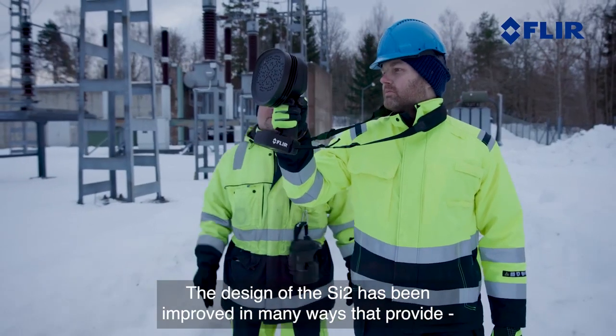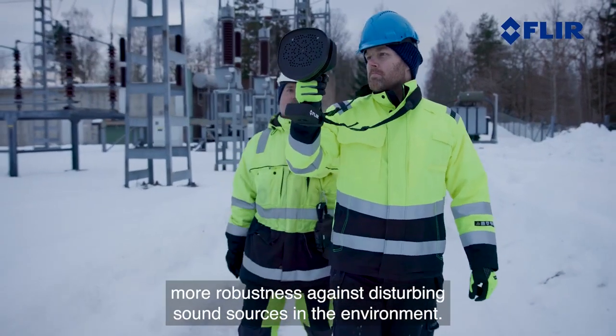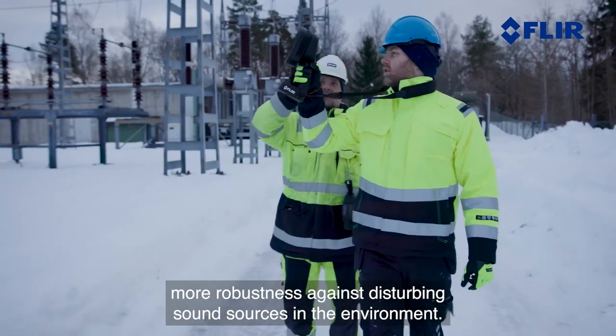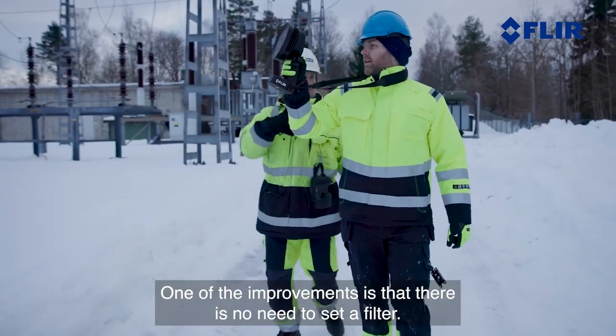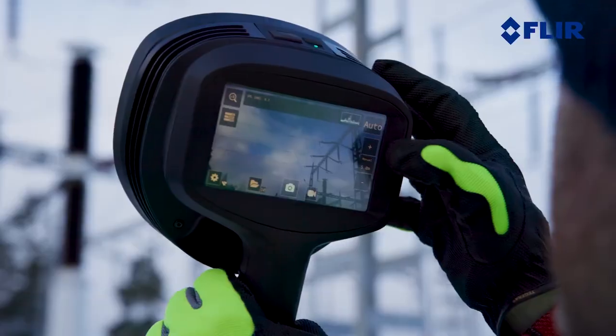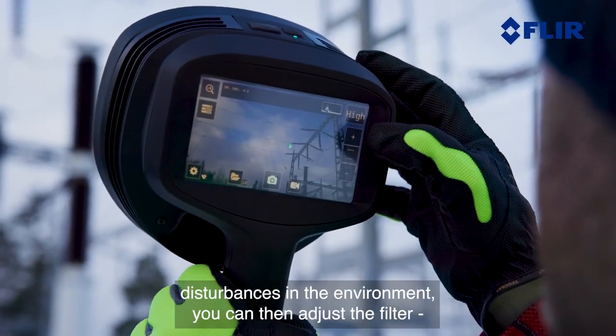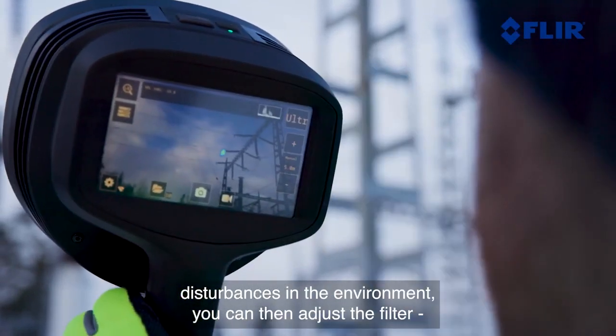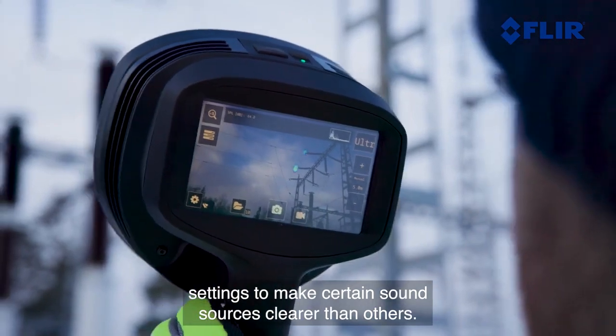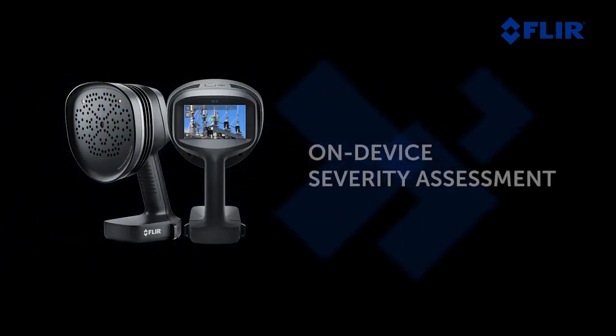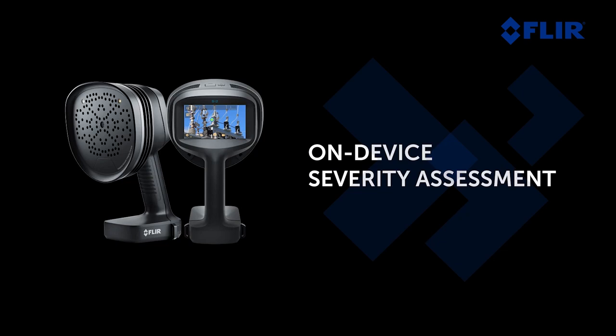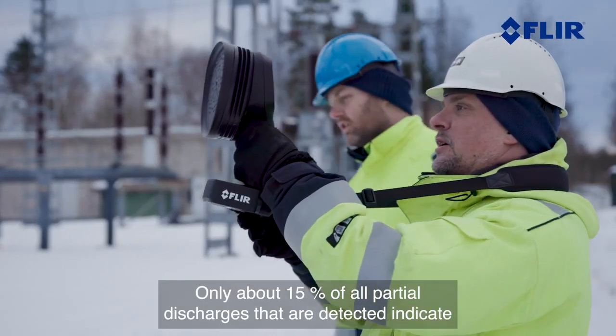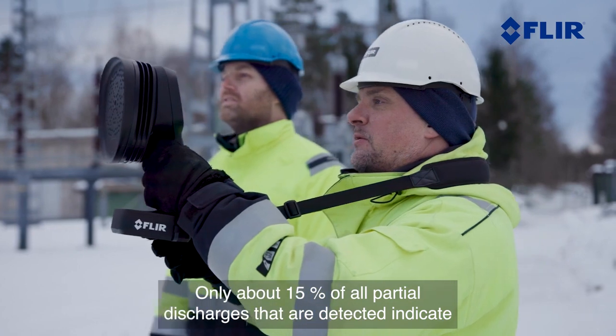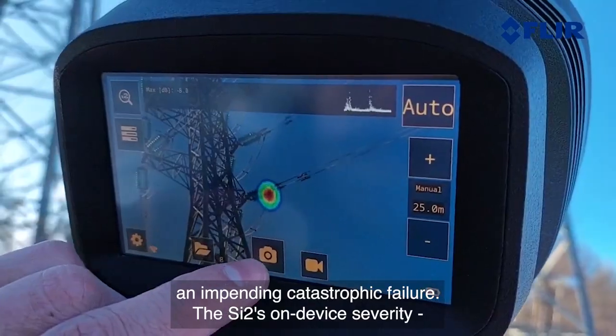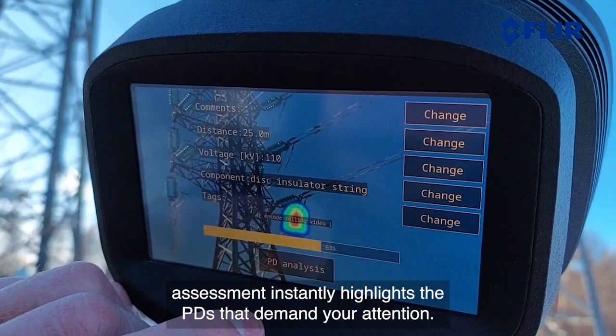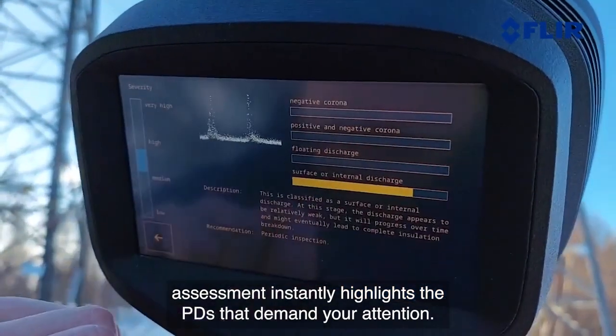The design of the Si2 has been improved in many ways that provide more robustness against disturbing sound sources in the environment. One of the improvements is that there is no need to set a filter. However, if there are significant noise disturbances in the environment, you can then adjust the filter settings to make certain sound sources clearer than others. Only about 15% of all partial discharges that are detected indicate an impending catastrophic failure. The Si2's on-device severity assessment instantly highlights the PDs that demand your attention.